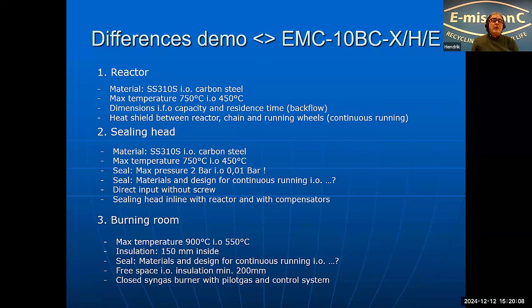So the burning room, we also changed so that we can have temperatures of 900 degrees, and we put insulation inside, high temperature insulation, about 150 millimeters inside, and the seals will be designed now also for continuous running. On the outside, we have enough free space to make insulation of minimum 200 millimeters to get a maximum outside temperature of about 40 degrees.